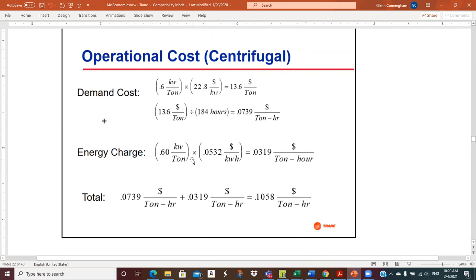So we can add it to the energy charge, which we have to get all this on an hourly basis. So they say this is what the demand charge would be, $13.60 per ton, but we're going to spread that over the 184 hours that this thing operates. So we get about 7.39 cents per ton hour on the demand cost.